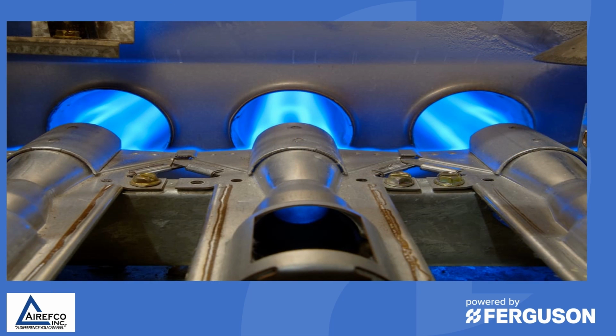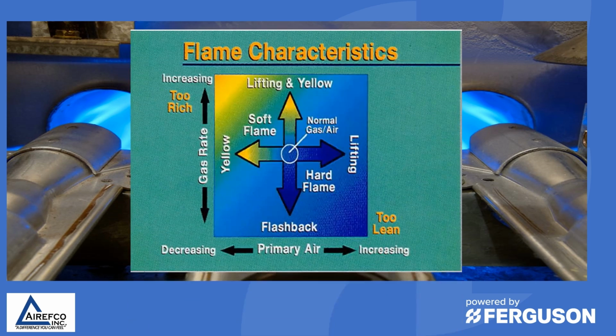So our main goal in tuning up a furnace is to make sure that we have a good blue flame and that it is being drawn down the heat exchanger tube the way that it should be for proper combustion. We want to make sure that we have the correct gas rate or the gas pressure and the proper primary air so that we can achieve this flame characteristic.